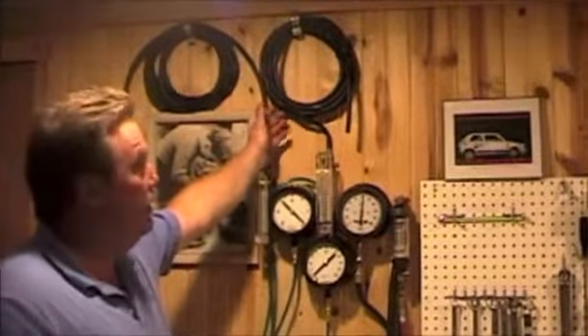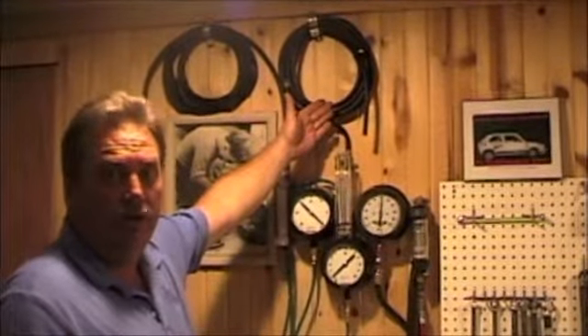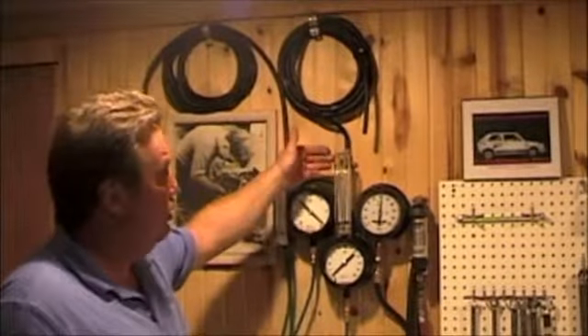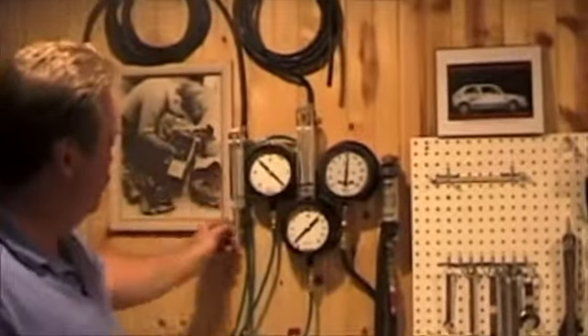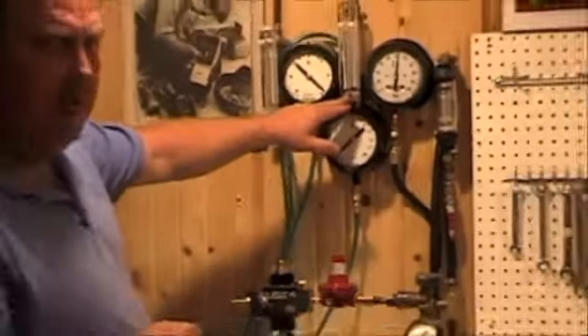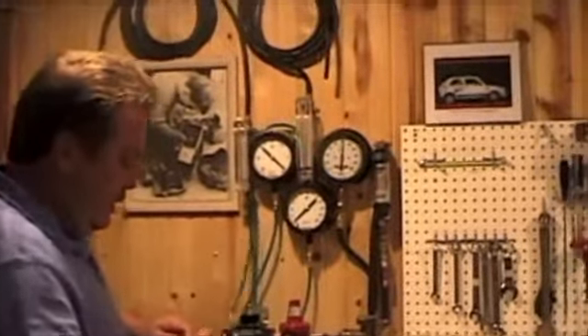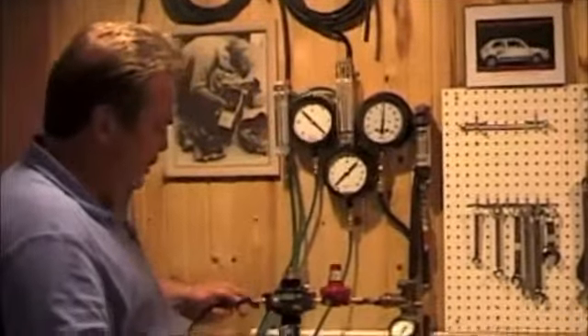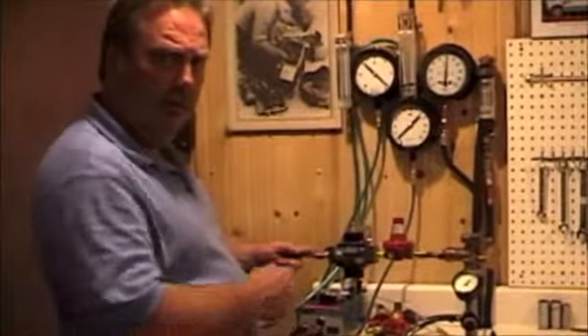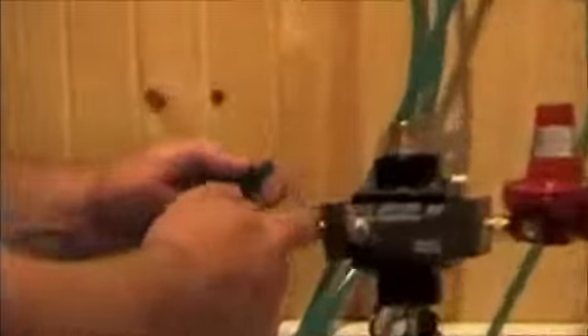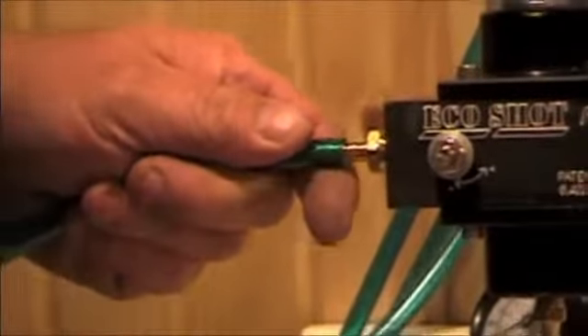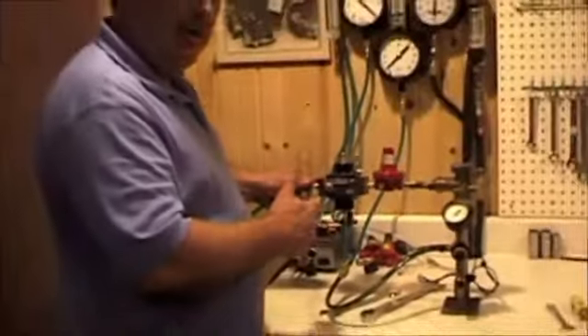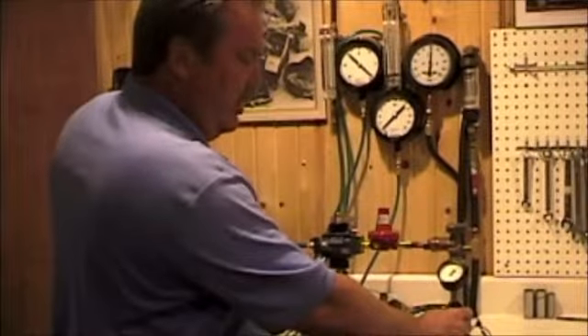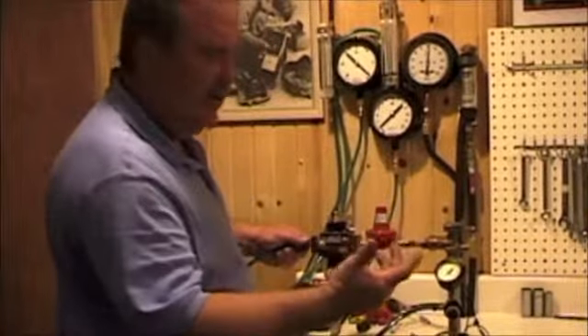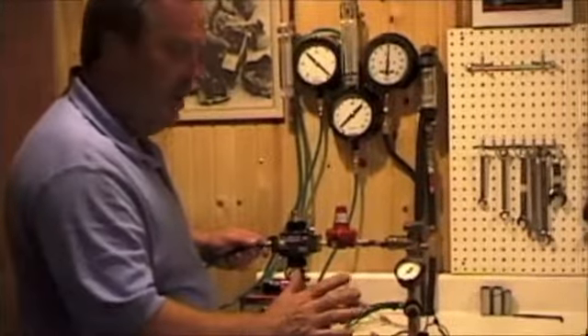We want to be very accurate, so we put it back in the same amount of hose that you'll be having, or very close, through the flow meter. And I have one hose right here that just connects to the bottom of the flow meter. Now, to know how much flow we're going to get, I'm going to put this on the end, on the outlet line. This would be propane delivery to your airbox, but you'll have the hose off of it. And for your purpose of checking start time, you'll have it off. Now, if I am setting this unit up, we have a 5-pound start time. That's where we left it at. So that means it starts to flow propane at 5.